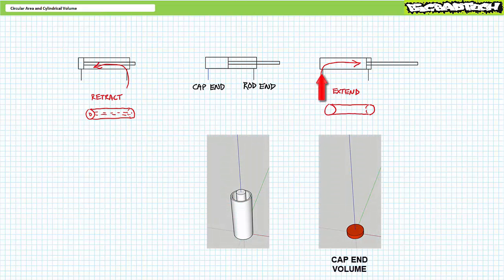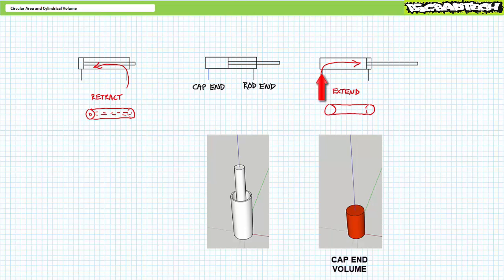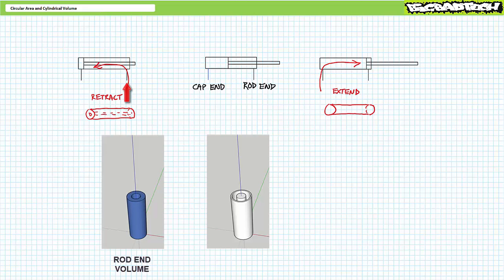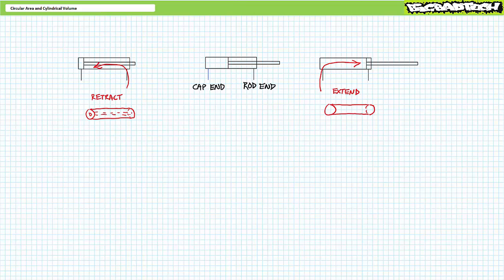When extending, fluid must fill a fully cylindrical cap end volume and pressurized fluid acts on a fully circular area. However, when retracting, fluid fills a smaller tubular rod end volume and pressurized fluid acts on a smaller ring-like annular rod end area. Take note of the terminology: the fully cylindrical side used to extend the cylinder is called the cap or blind end, whereas the tubular side used to retract the cylinder is called the rod end — or annular end.